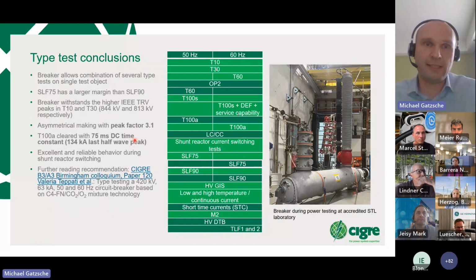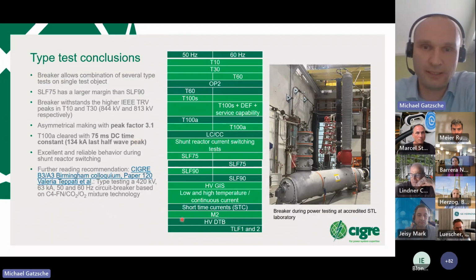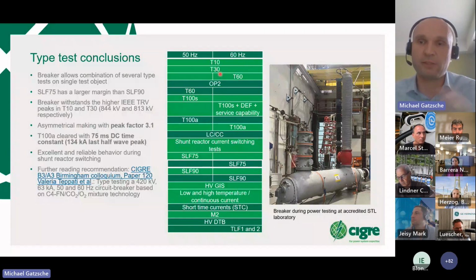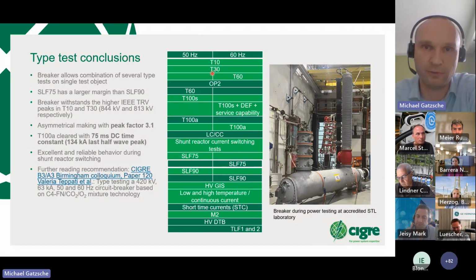To summarize the type test, you see here the big table of all the type tests. Some fields have the same color and are adjacent to each other, meaning that this type test, because it's such a big series with 50 Hertz, 60 Hertz, IEEE, IEC, were done on the same test object.